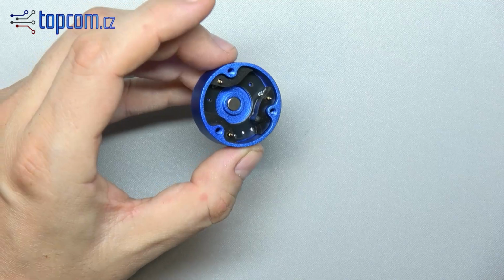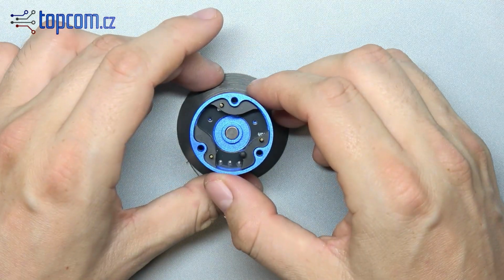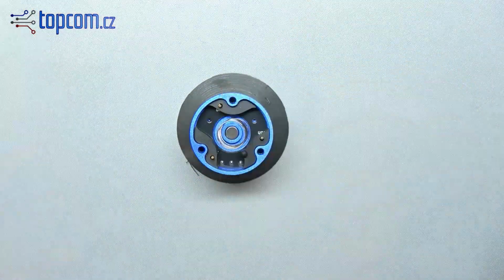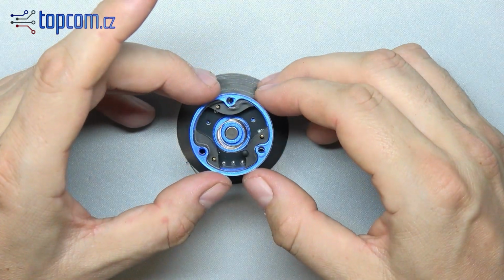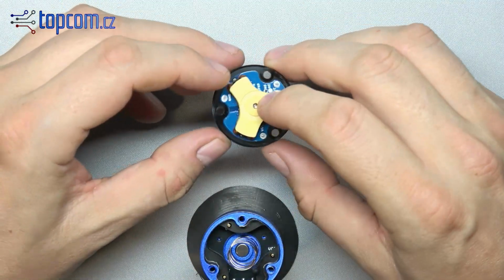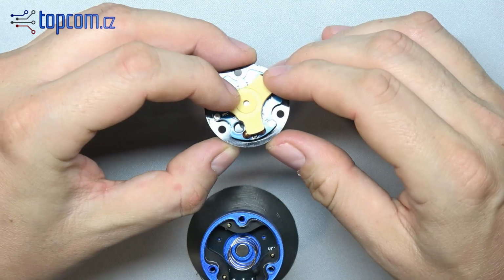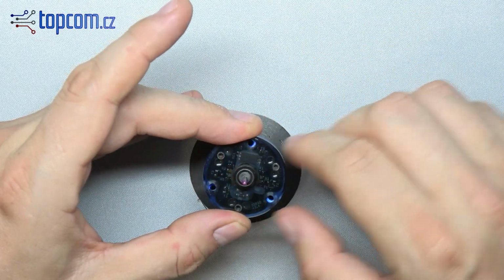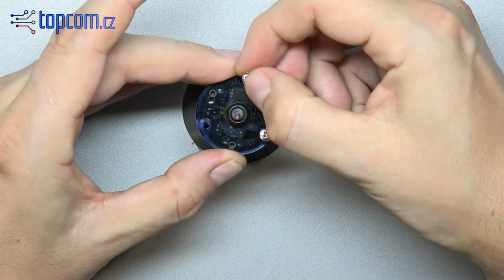Locate the anti-rotation pin on the probe housing. Insert the spring into the body followed by the spacer, and then press in the sensing assembly so that the anti-rotation pin aligns with the hole in the PCB. Insert the 3 screws back into the bottom side of the probe and tighten them.